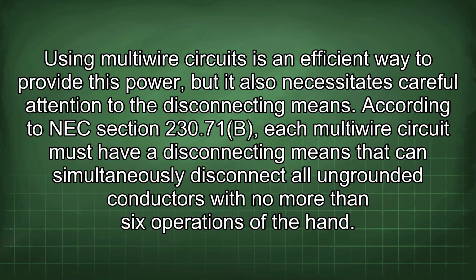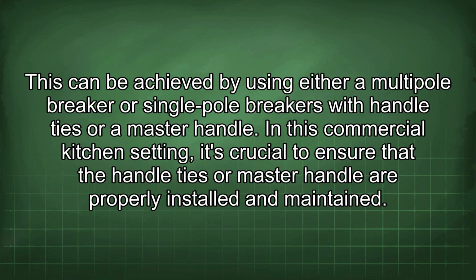230.71(B), each multi-wire circuit must have a disconnecting means that can simultaneously disconnect all ungrounded conductors with no more than 6 operations of the hand. This can be achieved by using either a multi-pole breaker or single-pole breakers with handle ties or a master handle.